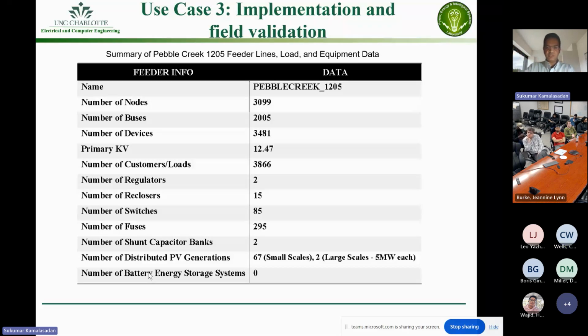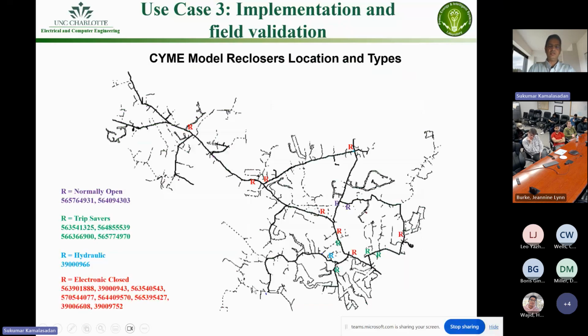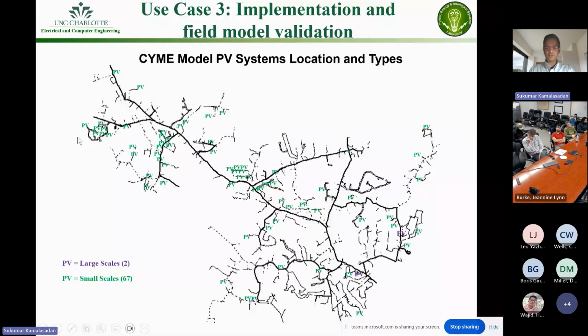The system does not have battery energy storage, so we included the controllable asset as a battery co-located with that large-scale PV farm. Here is the network information with the number of reclosers, fed from 2 different points at 2 different locations, so there is flexibility to power from 2 different sources, serving both the large PV and the small PV locations.